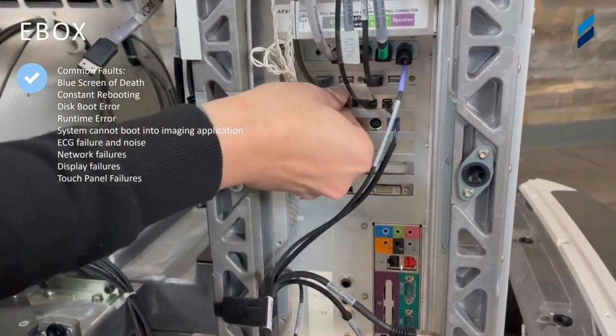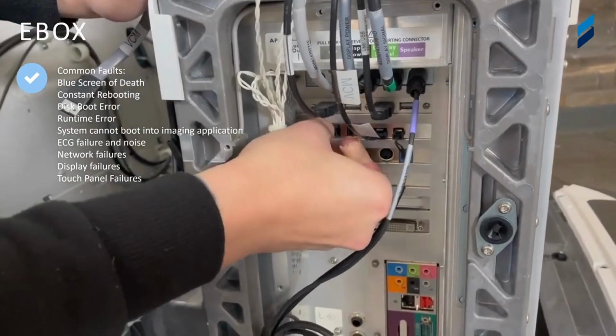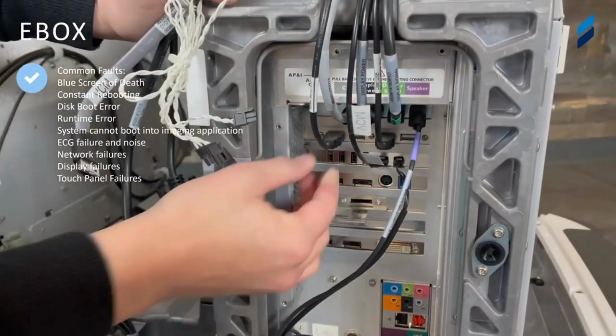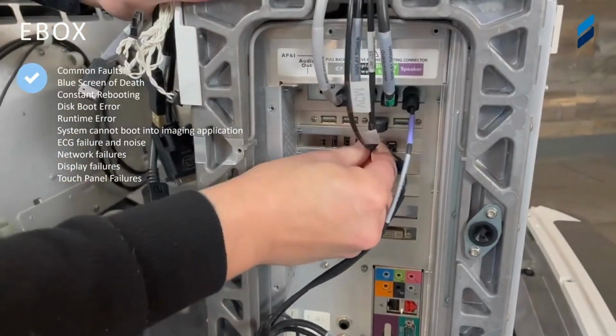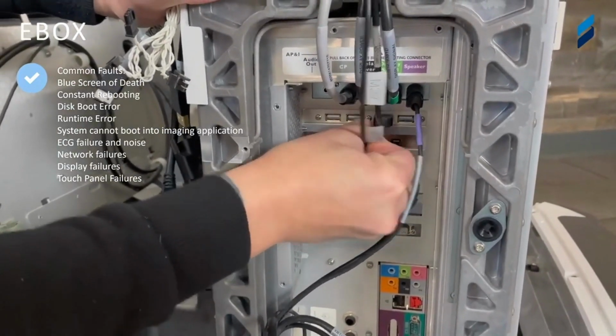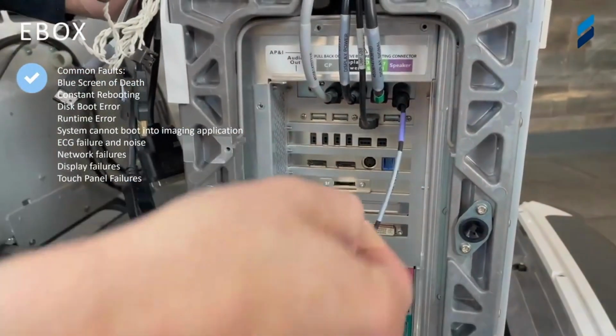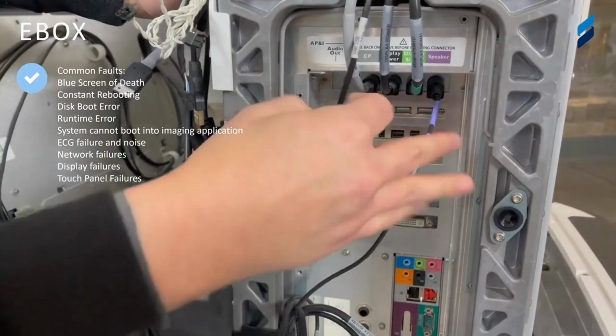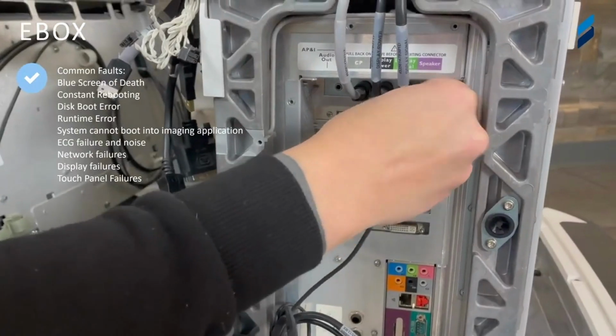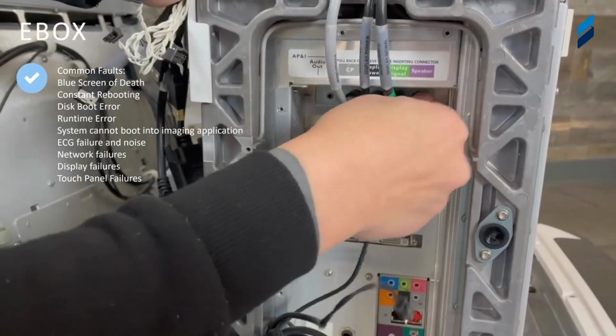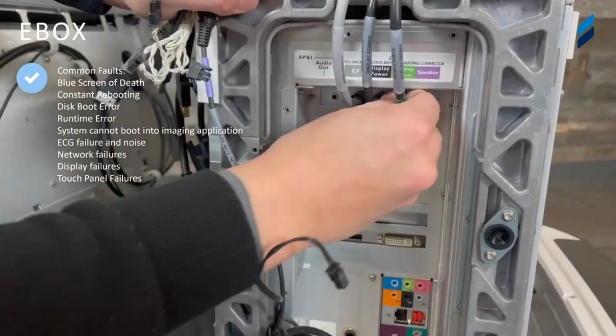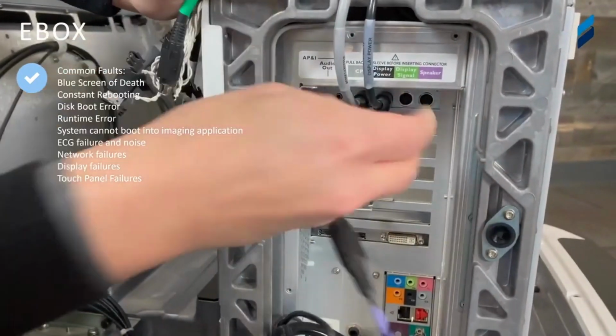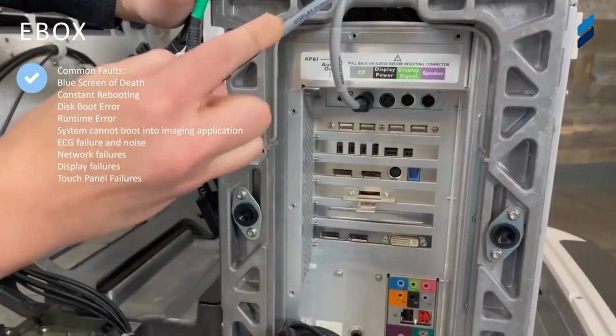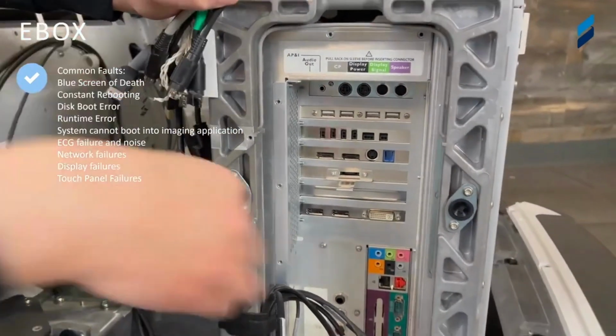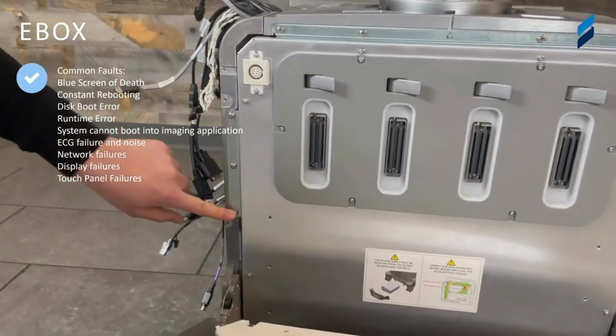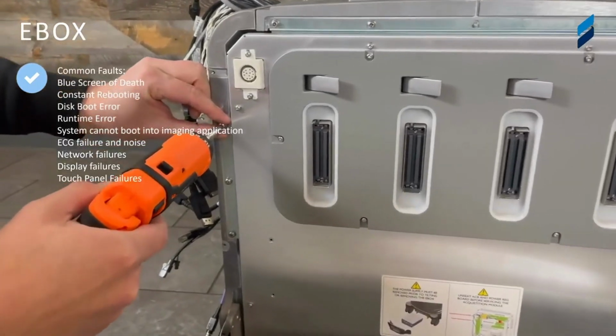So you can see everything is connected to the Ebox. And we're getting to fan speed connectors here. USBs, make sure that you mark which one goes where because it does sometimes bark at you if the USBs are in the wrong spot. And you can see above our hand here that there are some indicators of what cables go to what and what they are, some color coding, but it's definitely not complete to the rest of the cables that we removed here shortly before. All right, let's get those cables out of the way.